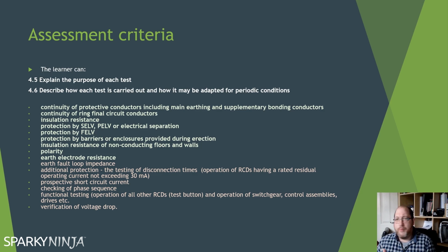We have terms like breaking capacity. If you look at a circuit breaker, you may see 6,000 or 10,000 in a rectangle. Go to an old one, the 3871, it might have M9 written on it or something like that. But yeah, these are the levels of capacity of current that the device can tolerate and still remain in service. If we exceed that, it'll probably work, but no longer actually work after a single event.